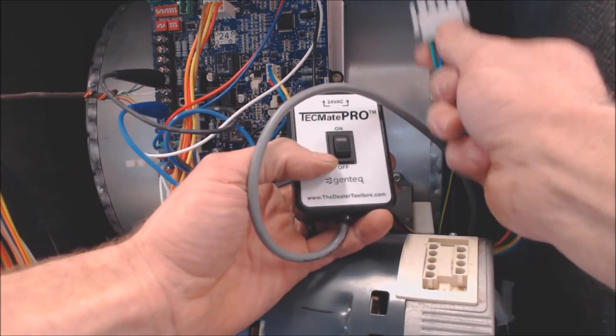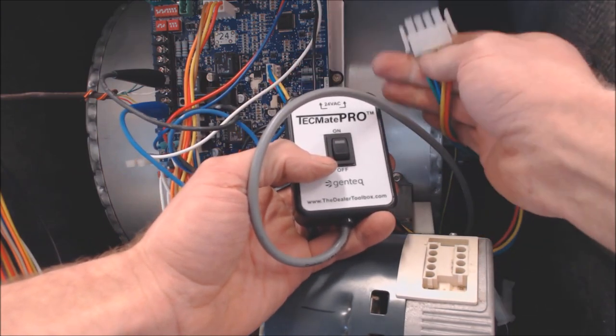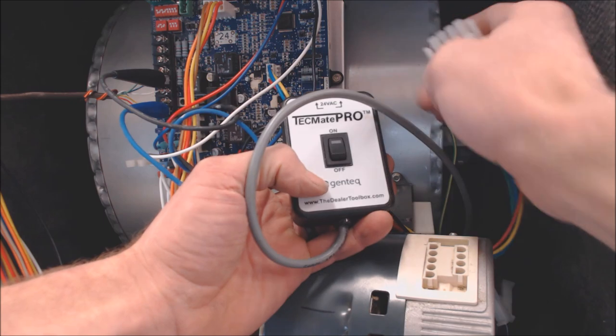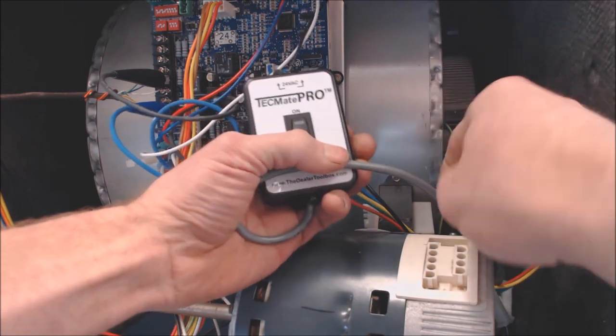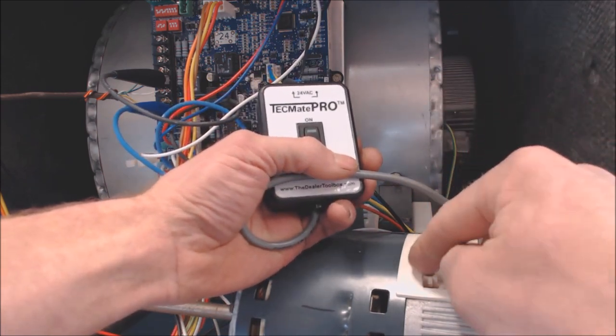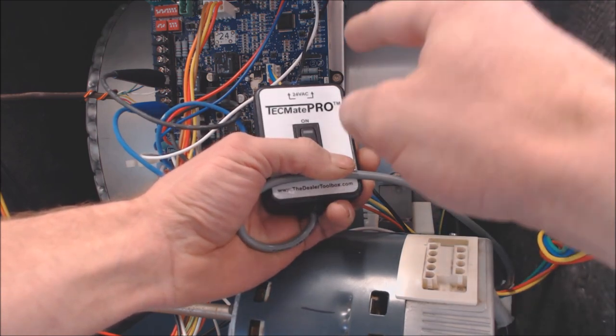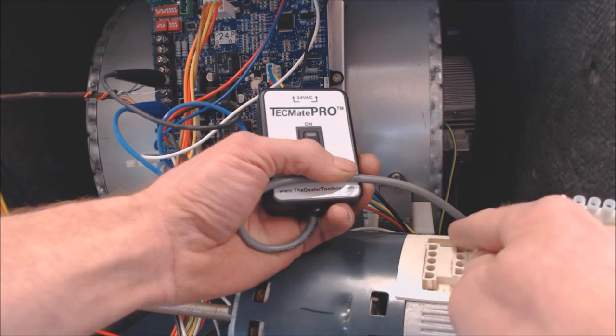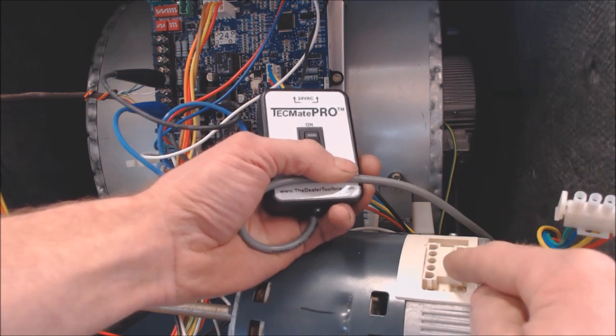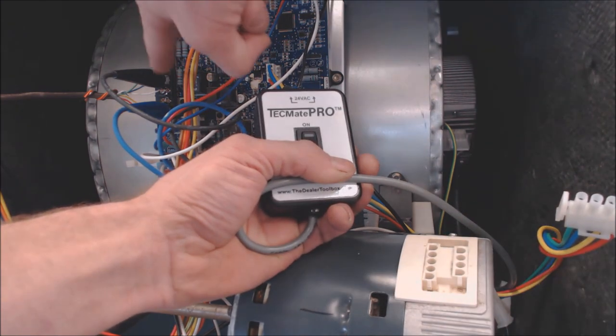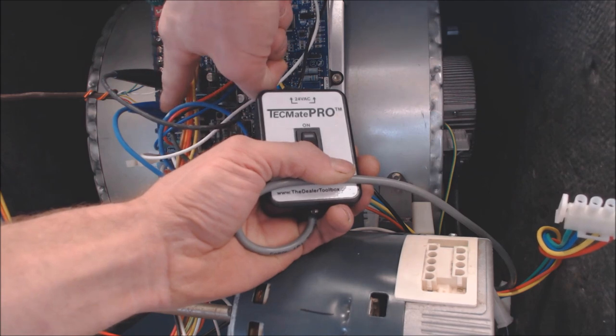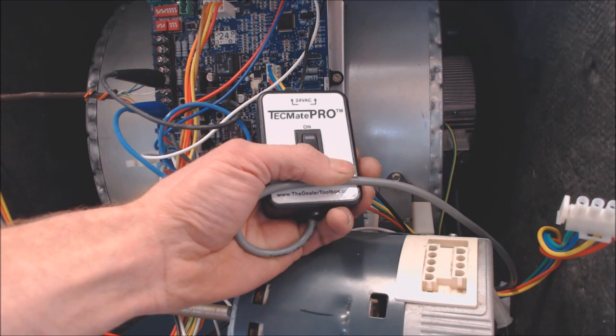So presently, we have our connection from the board disconnected to the variable speed blower motor. We have the 120 volt power wire, which would be the ones connected right here. That's still connected onto the blower motor. So we have the TechMate Pro plugged into the second set of pins, which is the four pins. We have one connection on common, one connection on 24 volt hot. And now we're going to go ahead and turn the furnace on.